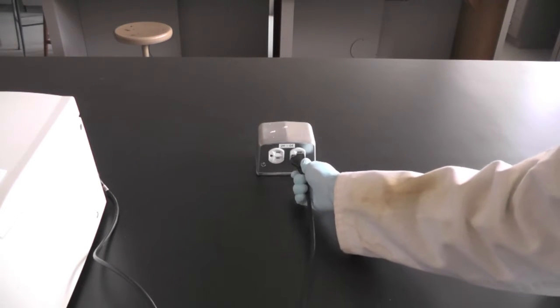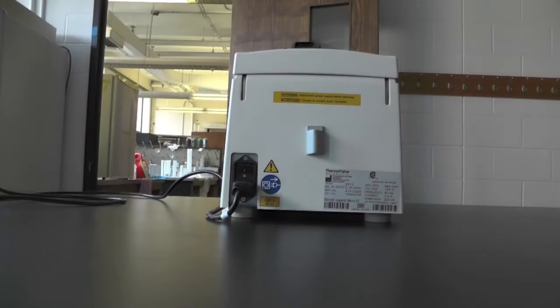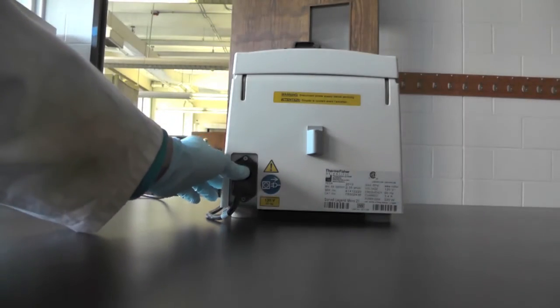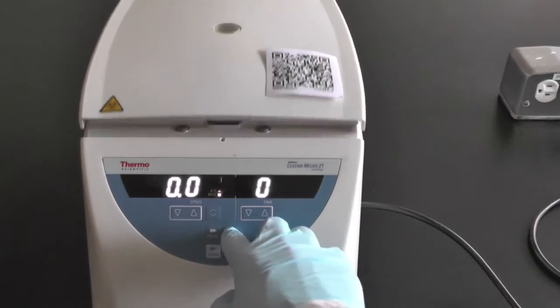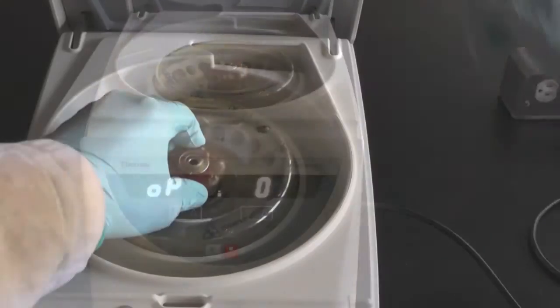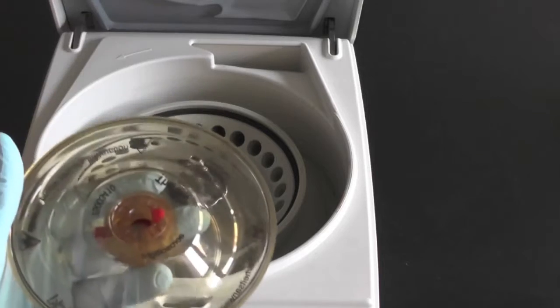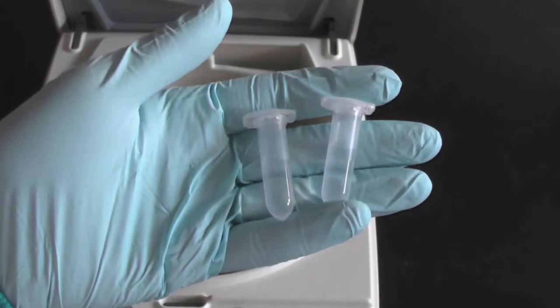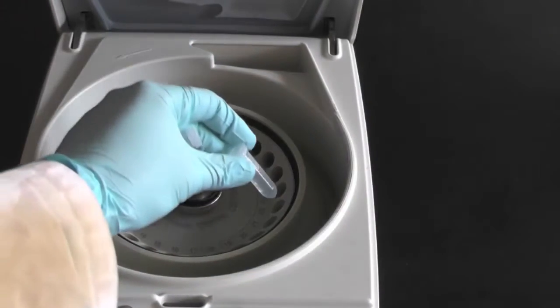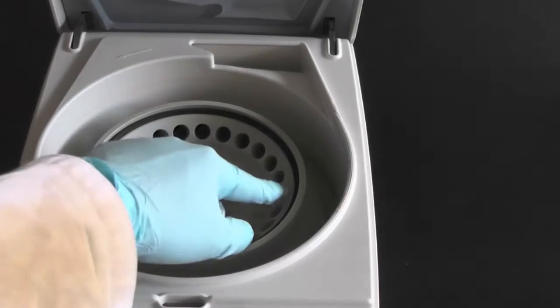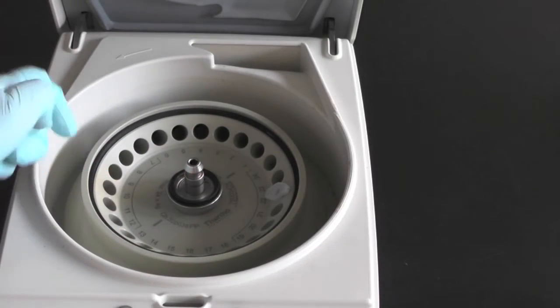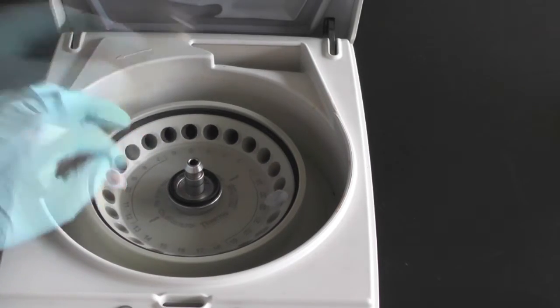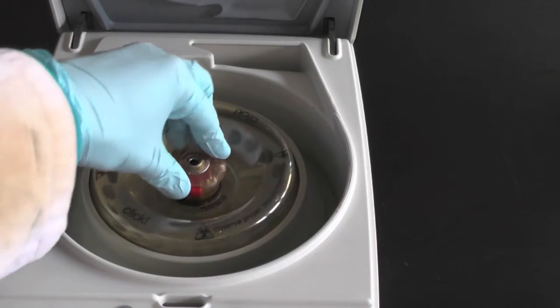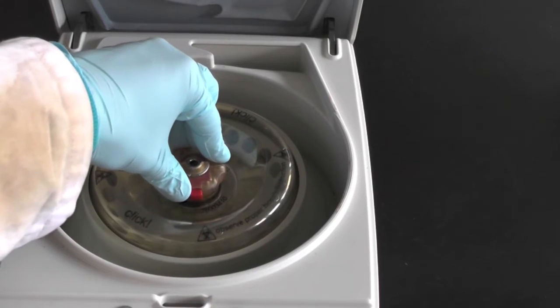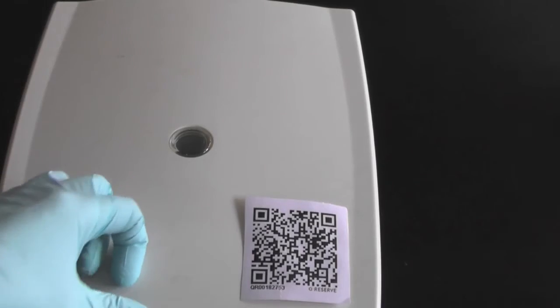First, plug in the machine and turn on the power by turning on the switch at the back of the machine. Open the cover. Remove the inner cover by holding down the red button on the lid. Insert the microtubes filled with samples into the sample slot. At least 2 microtubes have to be inserted and must be placed across from each other to balance the centrifuge. Cover with the inner cover and press on it until you hear a click. This makes sure it's tightly locked. Close the outer cover and make sure it's locked as well.